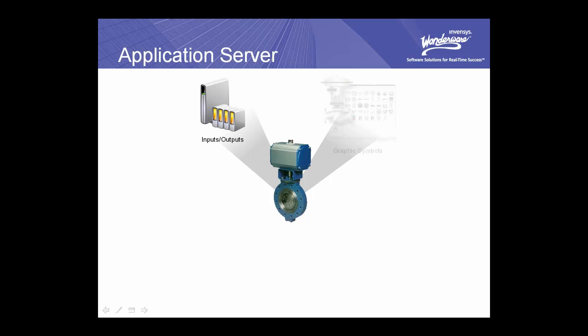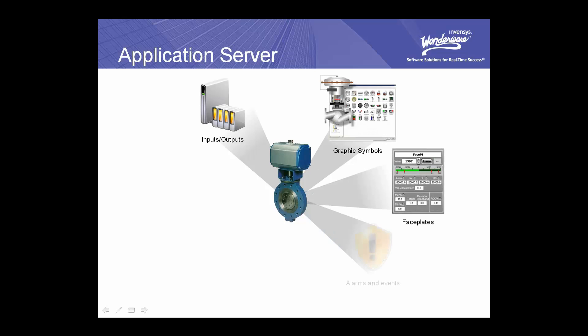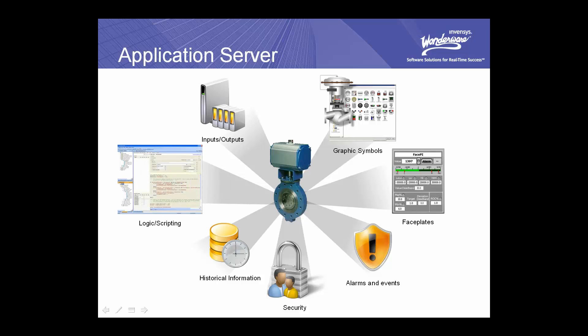Let's start by looking at the foundation on which System Platform has been built: the product called Application Server. This product provides system designers with the ability to define all the related elements of an asset or device, such as the I/O points associated with it, as well as any logic and scripts needed for the supervisory system to interact with the device. Within the asset definition, we identify what data points we want to store long-term for analysis, and we can also define who can operate and interact with the device — applying to both the runtime model and the design time model.